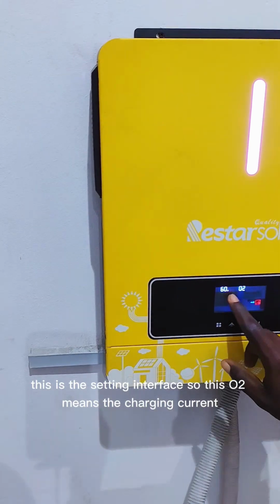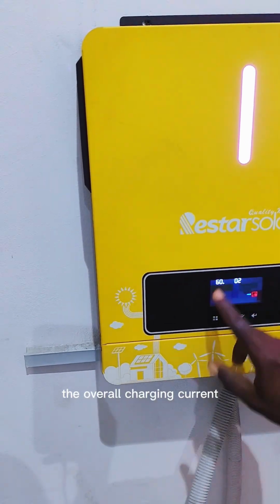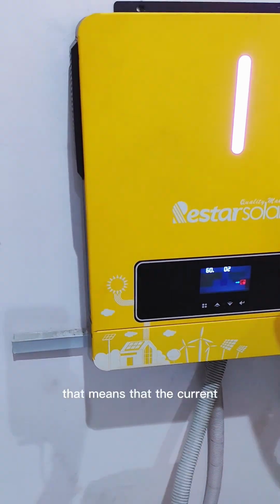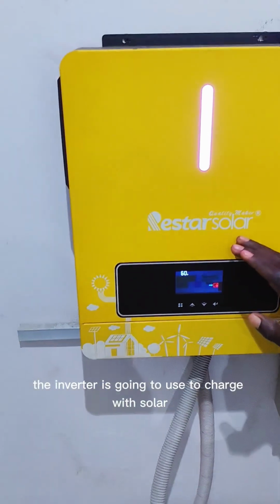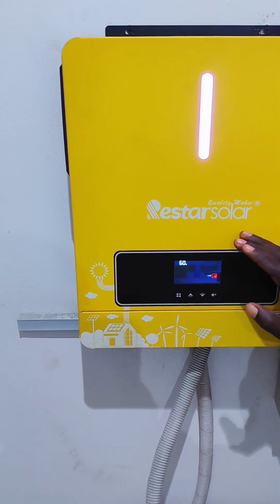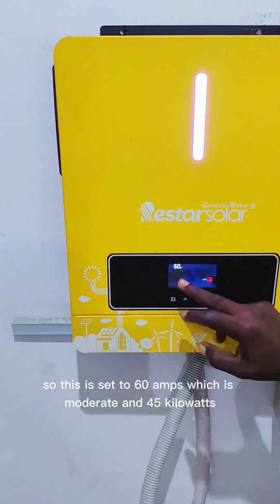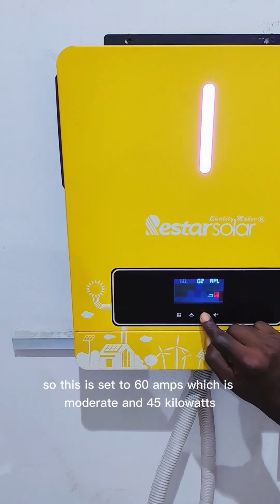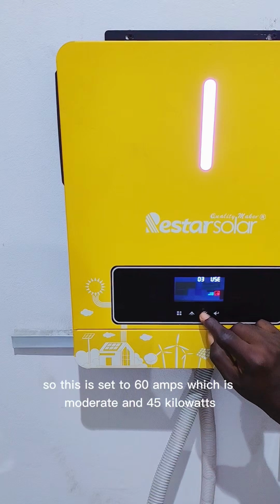So this 02 means the charging current, the overall charging current. That means the current the inverter is going to use to charge with solar and also electricity. So this is set to 60 amps, which is moderate for a 5 kilowatt inverter.